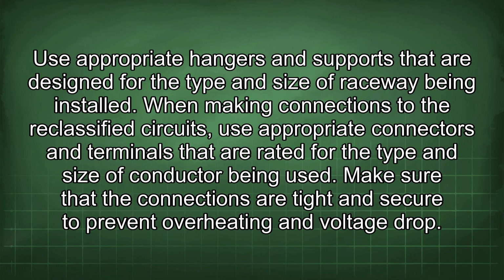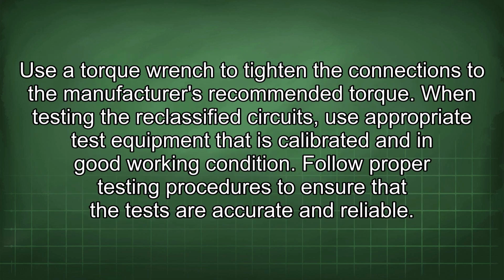When making connections to the reclassified circuits, use appropriate connectors and terminals that are rated for the type and size of conductor being used. Make sure that the connections are tight and secure to prevent overheating and voltage drop. Use a torque wrench to tighten the connections to the manufacturer's recommended torque.